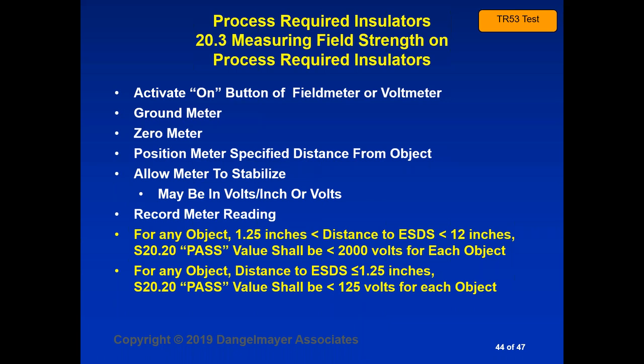So the ground cords that come with an electrostatic voltmeter have no resistor in them. They're just a direct connection to ground. Getting those confused with a wrist strap connector can have serious consequences for safety. So it really would be a good idea to make sure that any ground cord that doesn't have a resistor in it is marked very clearly and used only with something like the electrostatic voltmeter.